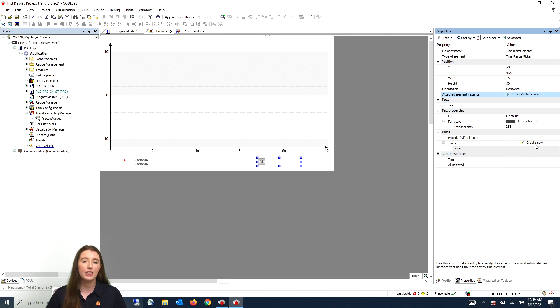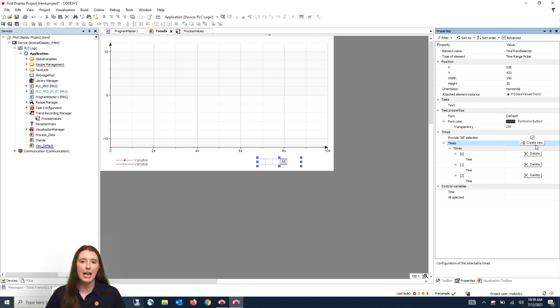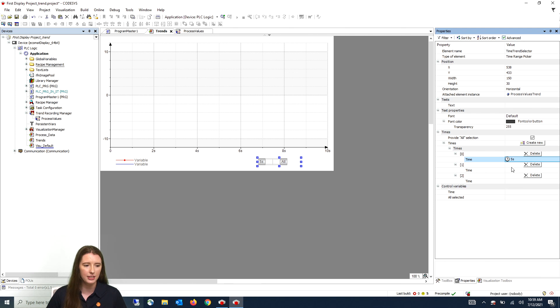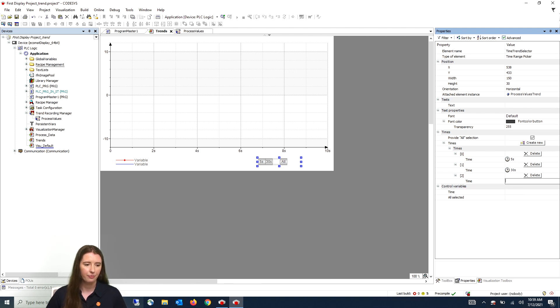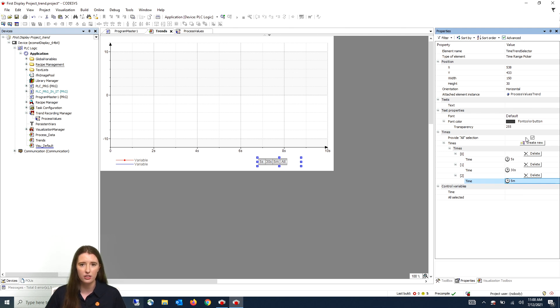Next we are going to click on the create new button three times to add different time windows. These windows can be set to any time frame — for my example it is going to be five seconds, 30 seconds, and five minutes. Make sure the provide all selection is checked, because this will allow you to zoom into the trend to look at different time window scales.